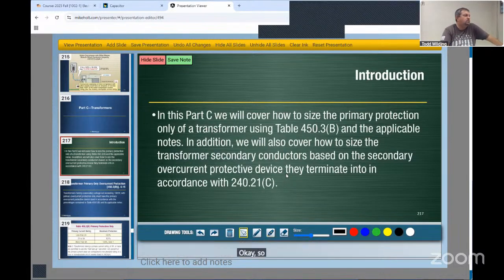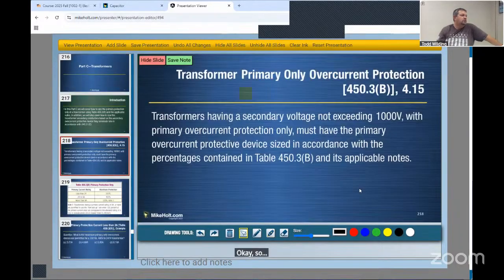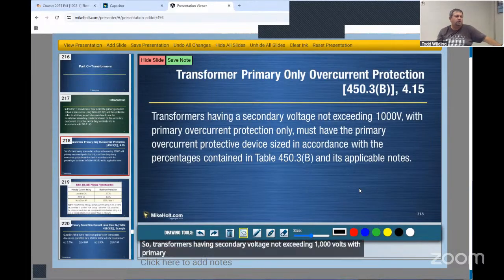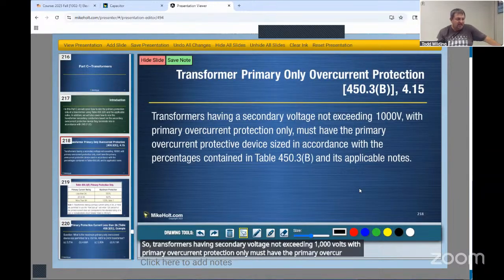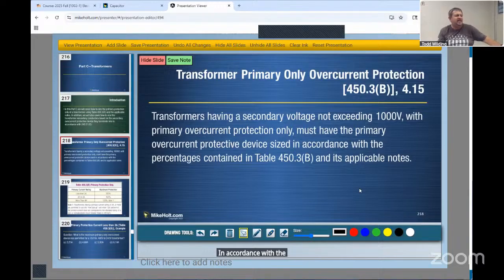Okay, so transformers having secondary voltage not exceeding 1,000 volts with primary overcurrent protection only must have the primary overcurrent protection device sized in accordance with the percentages contained in Table 450.3(B). So everybody go to their code book in Article 450.3. You should see a table there, and we want Table 450.3(B).